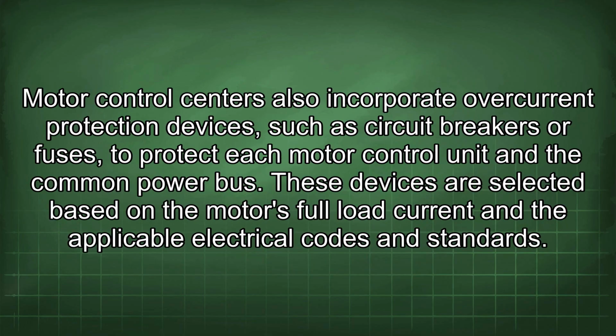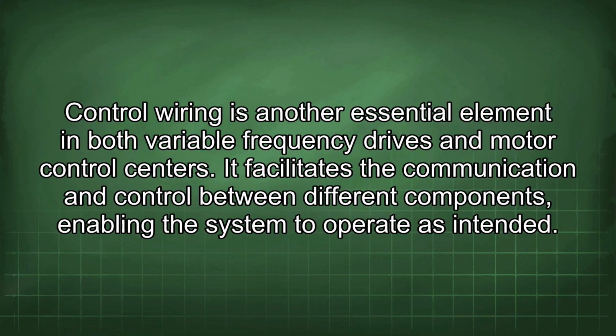Motor control centers also incorporate overcurrent protection devices such as circuit breakers or fuses to protect each motor control unit and the common power bus. These devices are selected based on the motor's full load current and the applicable electrical codes and standards. Control wiring is another essential element in both variable frequency drives and motor control centers. It facilitates the communication and control between different components, enabling the system to operate as intended.